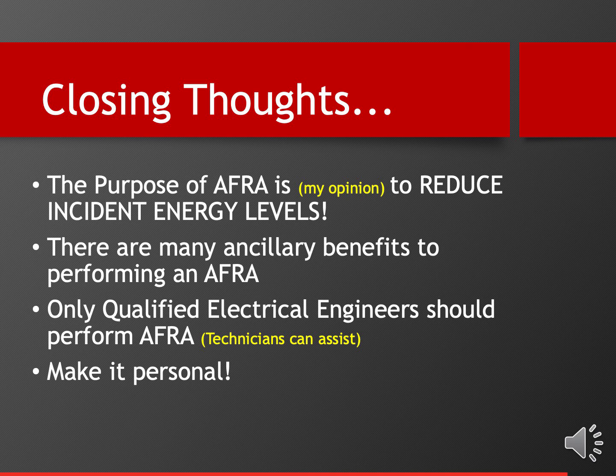There are many ancillary benefits to performing an arc flash risk assessment. We found devices that were seized in a closed position that were non-functional. We found things that had been changed in the field. There were sometimes whole circuits there that people didn't know were there. There are many benefits to doing the study besides just the incident energy calculation. Use only a qualified electrical engineer to perform the analysis, with help and assistance from technicians, which is a very great idea.